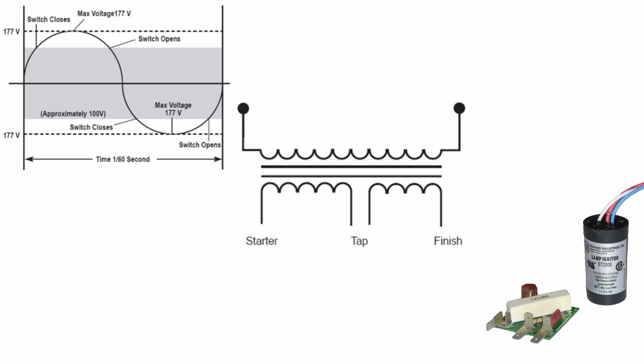Here's a key point. If your high-pressure sodium lamp is cycling on and off, it might not be the starter's fault. In fact, the starter could be working perfectly, trying to restart the lamp over and over. One common mistake: mixing starters, ballasts, and lamps that weren't designed to work together. High-pressure sodium starters come in different shapes. Some look like circuit boards, others look like plastic cubes, but they all do the same thing. That said, they're tuned to specific wattages and lamp types. If you mix the wrong ones, your lamp might start unreliably or not at all. Think of it like pairing a remote to your TV. Sure, it might turn on, but you won't get all the right functions unless they're made to work together.